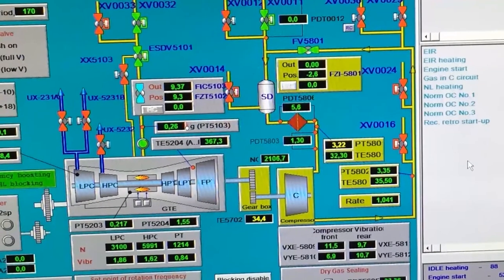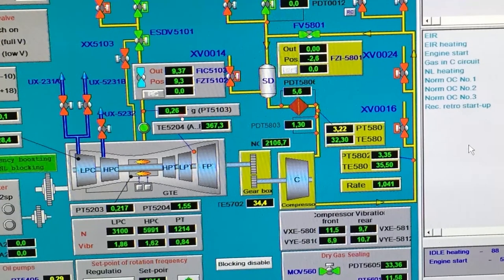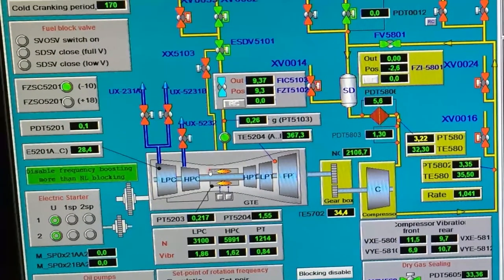You can see for example the different temperature and pressure of the devices from everywhere. For example here is the PDT actually for this case. It's a differential pressure of this one is just 0.1 bar. About the temperature you can find that in LPT of the gas turbine we have the actually degree centigrade of 367.